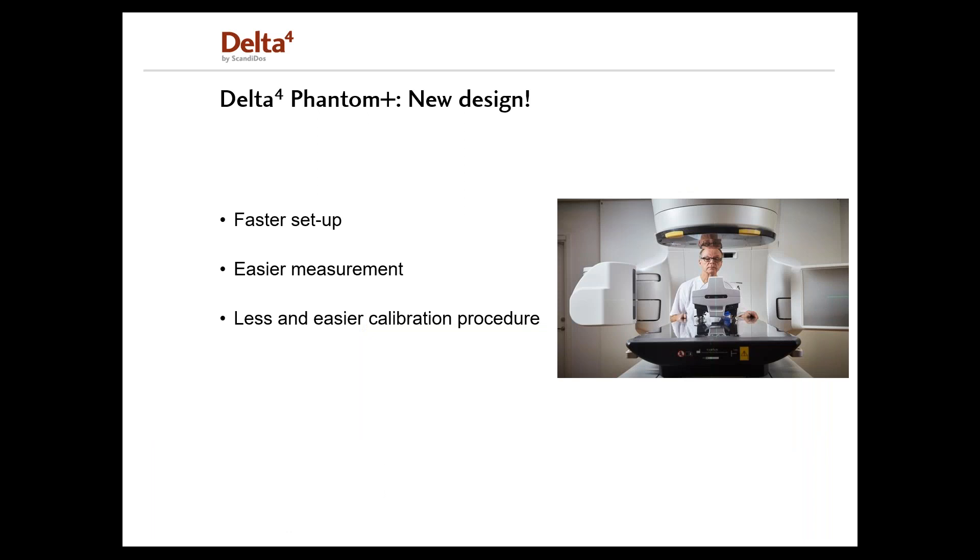ScandiDos has introduced the new Delta4 pre-treatment system, redesigned from the bottom up with next-generation detector technology. The Delta4 Phantom Plus offers faster setup, where alignment is done in seconds with clear markers on the Phantom for accurate positioning. Easier measurements, with the Phantom instantly ready without any warm-up — just turn on the power and you are ready to measure. With less and easier calibration procedures, at least six complex plans can be verified within an hour.